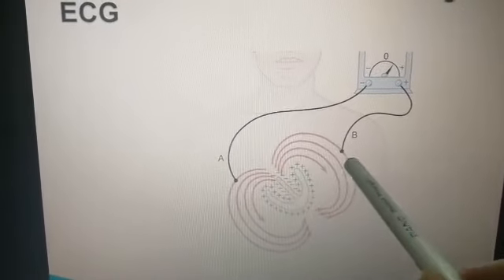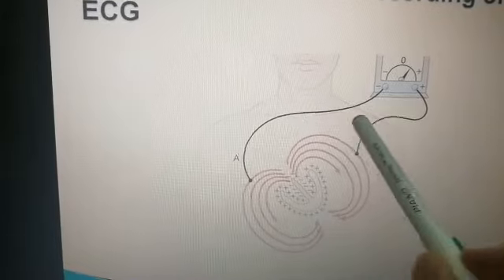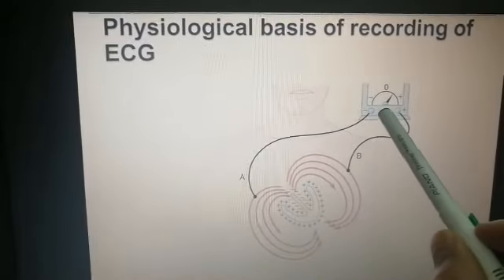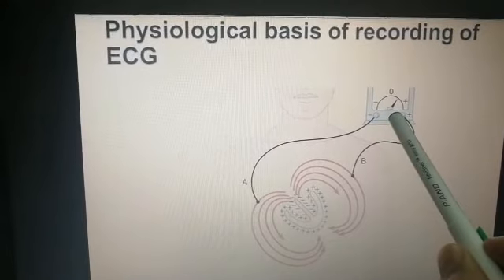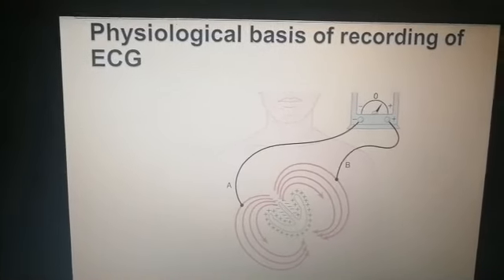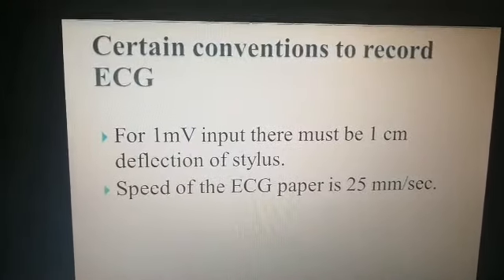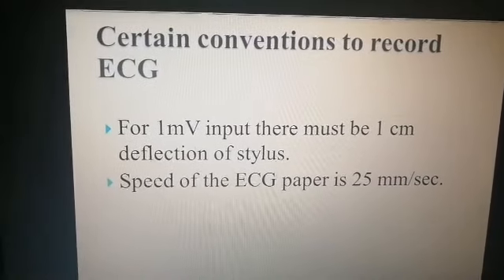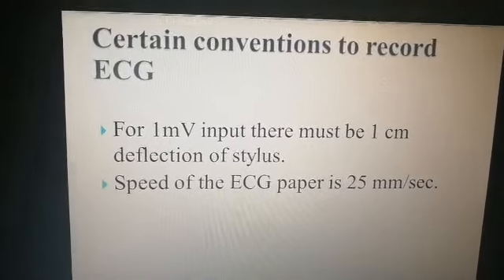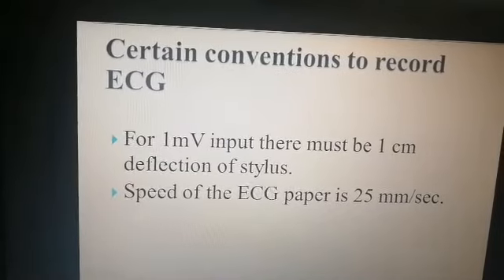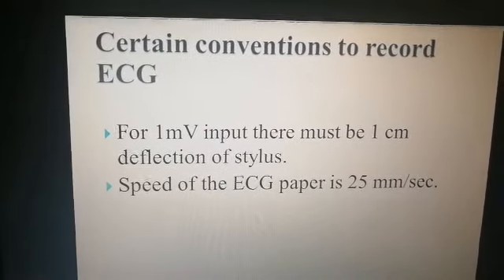The current in the heart comes to the surface of the chest, and from the chest the electrodes are connected to a voltmeter to determine the strength of that electric current. Certain conventions apply to recording ECG: for 1 millivolt input there must be 1 centimeter deflection of the stylus, and the speed of the ECG paper is 25 millimeters per second.